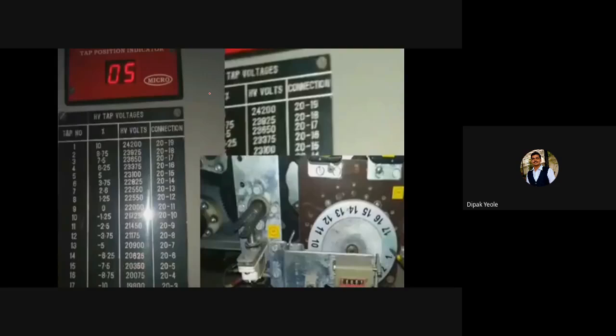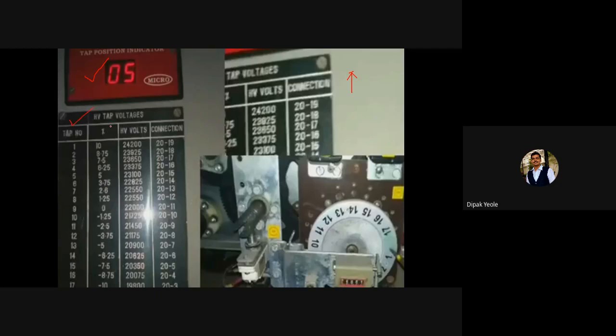This is the real picture which we have seen last time. You can see over here the indicator indicates the position, which is shifted from 1 to 5. We are interested to compensate the voltage, or you can say to boost the voltage, using the on-load tap changer. These are the traditional on-load tap changers available. There is a chart available on that particular on-load tap changer, and according to the tap number, we have to compensate the amount of percentage, and the appropriate transformation ratio is selected with the help of this on-load tap changer.